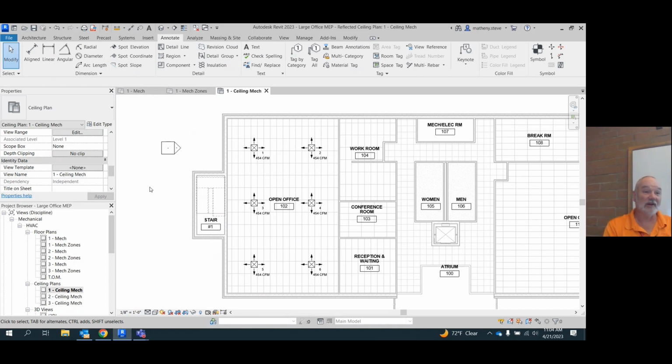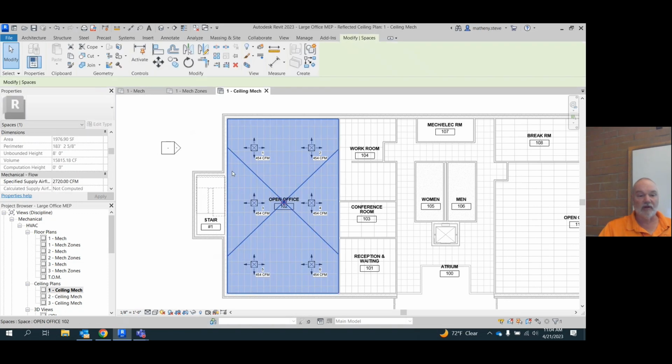They don't calculate it at all. No, but like right there, in the room. Oh, yeah. What it does is it just looks at how many CFM you use for each diffuser and adds them together. So we got 6 times 454. If you do that on a calculator, you're going to come out to 2724 or whatever that number was.